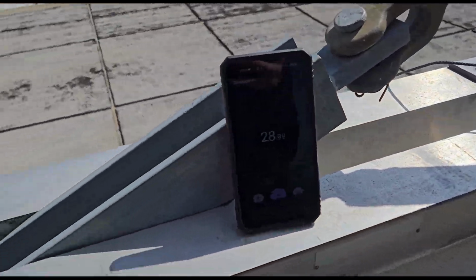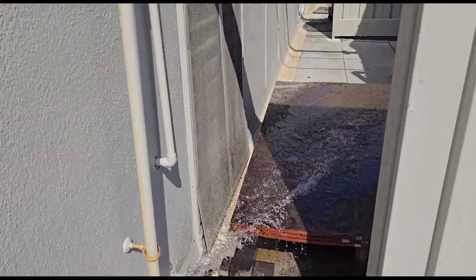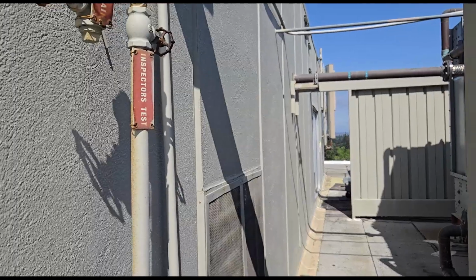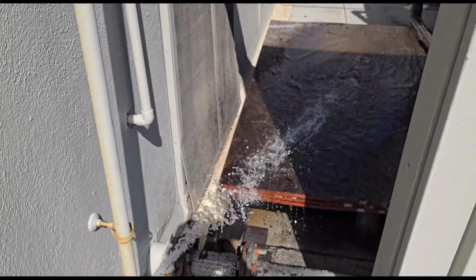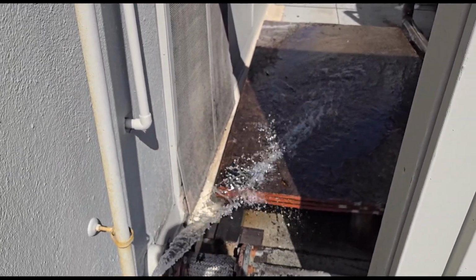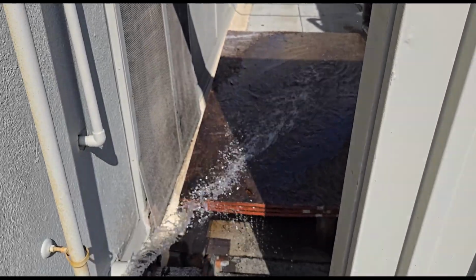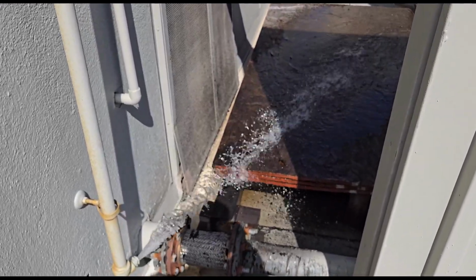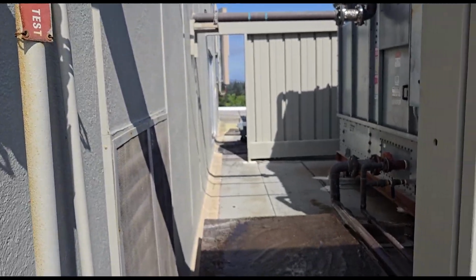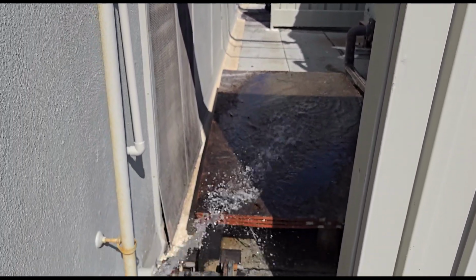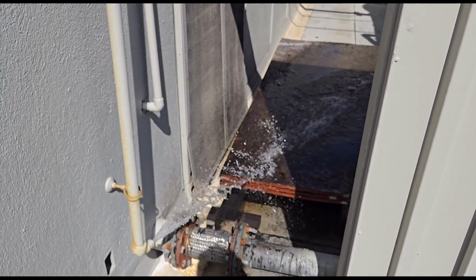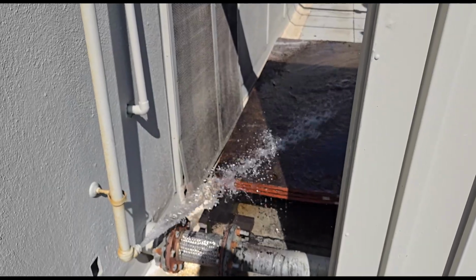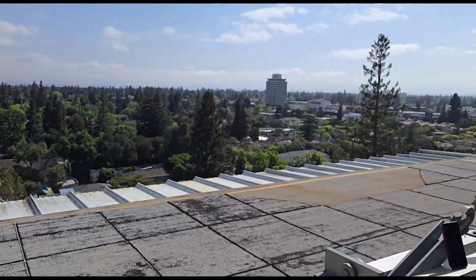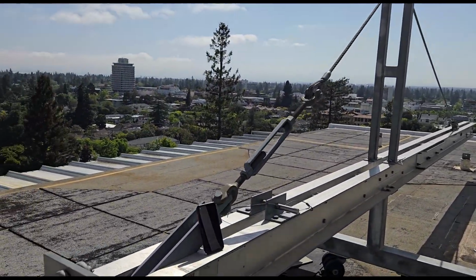About 30 seconds, and we're gonna run it to full 90 just because I'm solo on this job, so I don't have a technician at the panel. So I'll run it for my 90, make sure it came in. I could verify on monitoring the time afterwards. And then we will go back to the panel, verify we got our signal, verify that the jockey pump and everything's running.